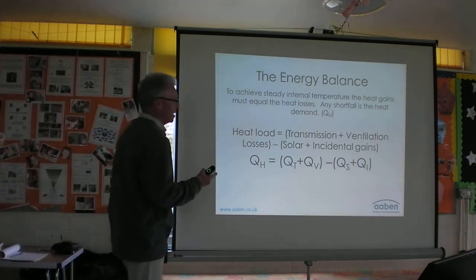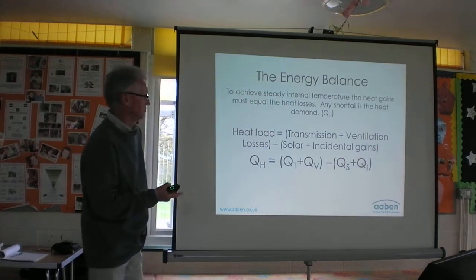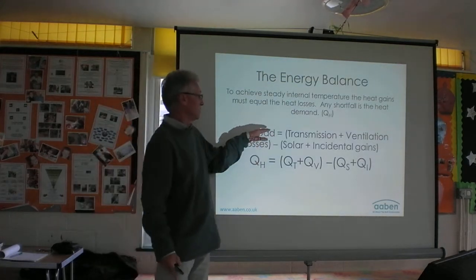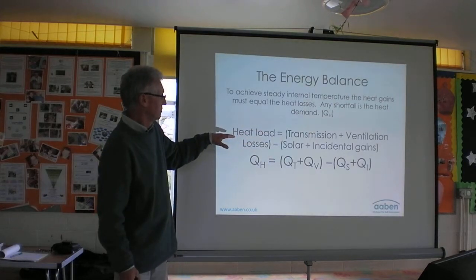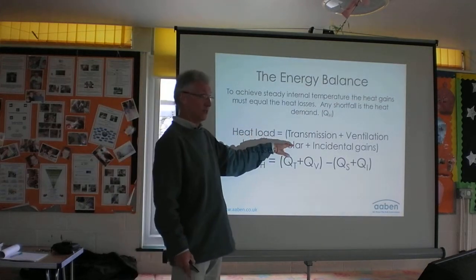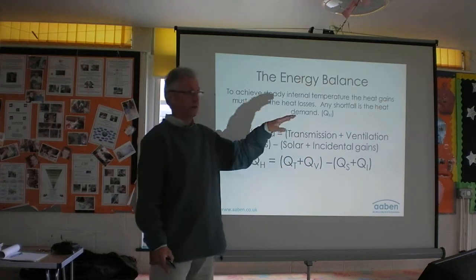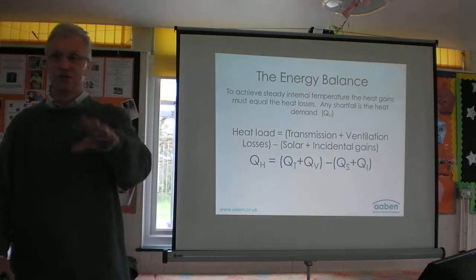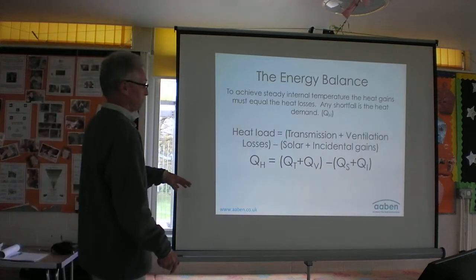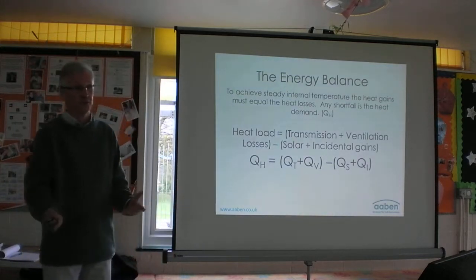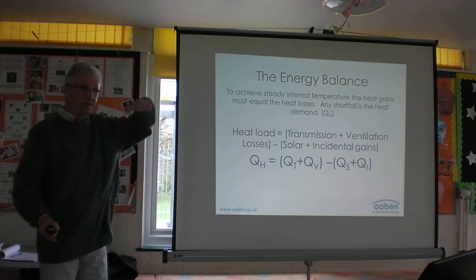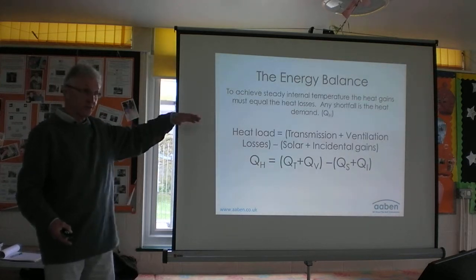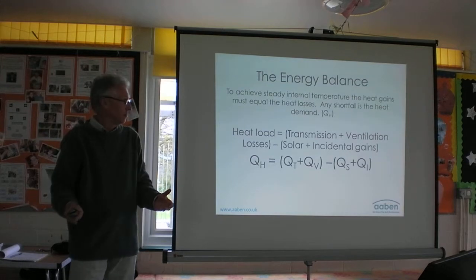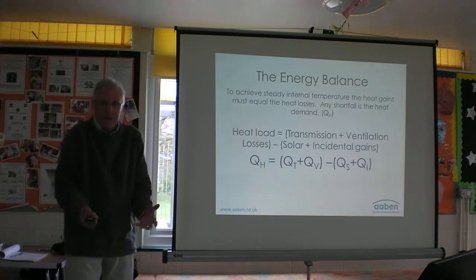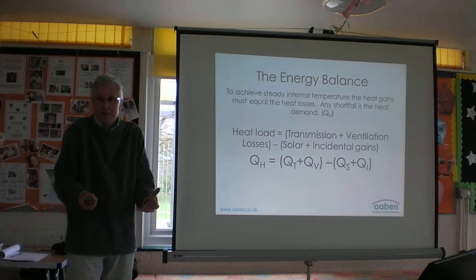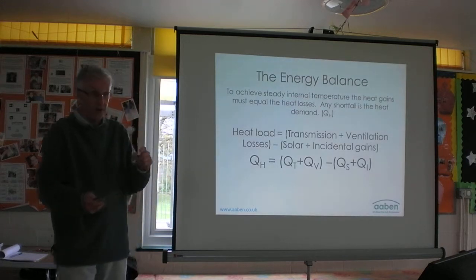It's about balancing up 4 things. The heat load, that is the losses through transmission and ventilation, and the gains from the sun and from other things. Your computer, your cooker, the dog, you. And the difference between those two is how much heat you've got to put in. So you get rid of all your losses as far as possible through the walls and through air, and you keep hold of all the gains that you've got, and the balance is small. That's all you've got to put in. It's only small in the winter.